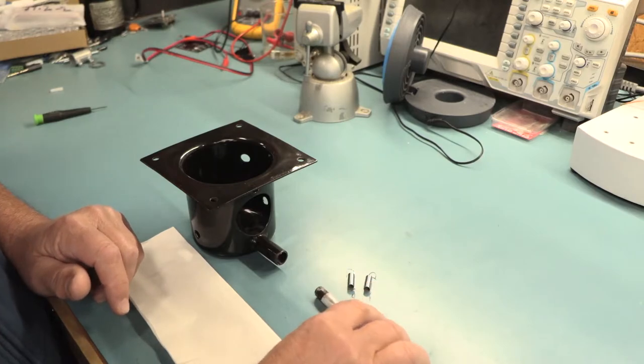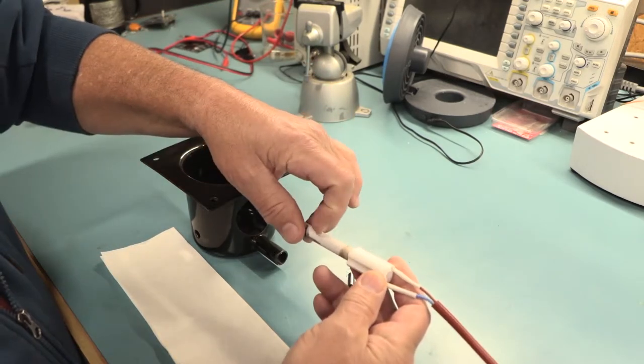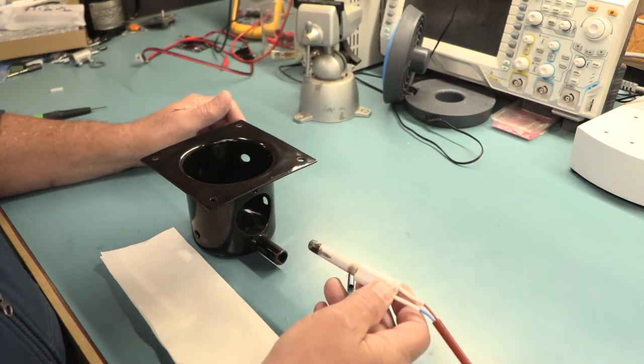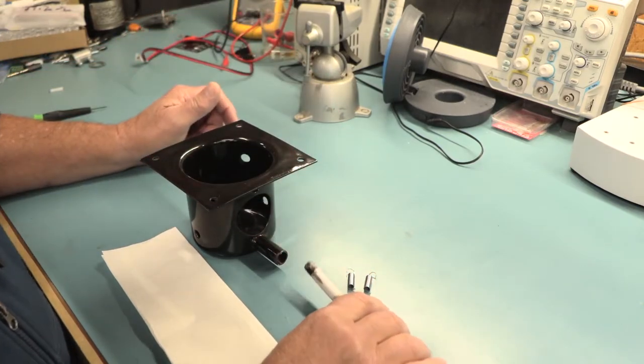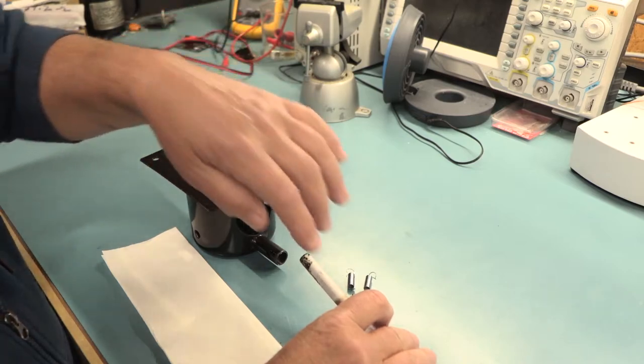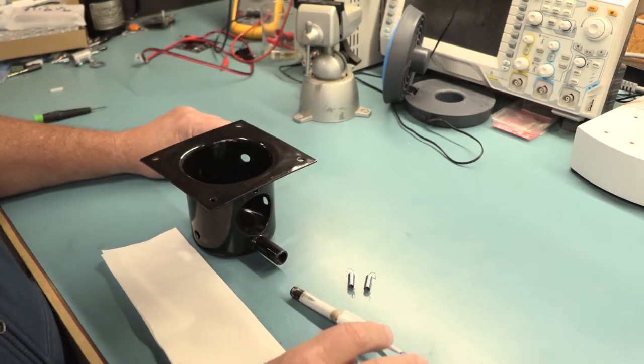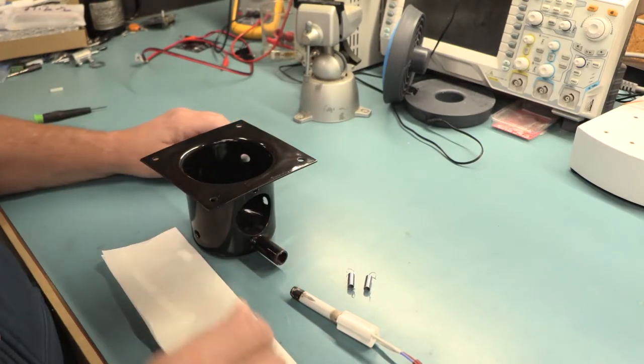So when you go to install the ceramic igniter, these things are durable. It's not like steel and they're not going to rust, but it's also ceramic like your toilet. So you don't want to be banging on it or you're going to chip it. And if you chip the ceramic, I guarantee it will burn out. It'll be just a pop—you'll hear a pop and it's gone.